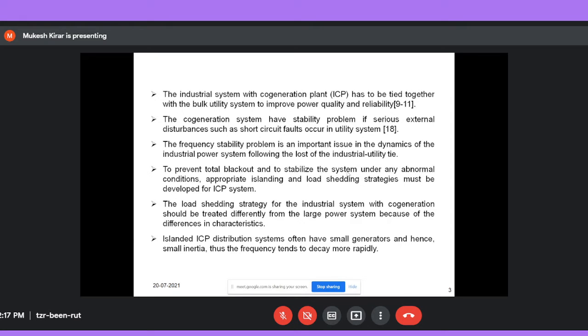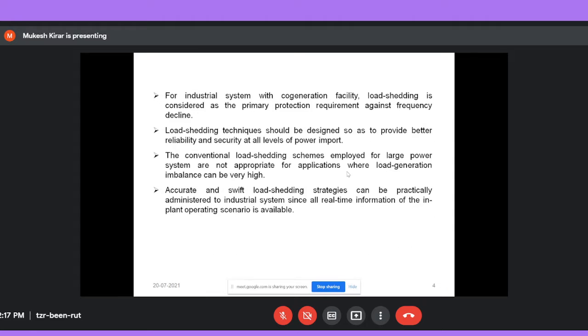At the same time, if there is an excess of generation and less load, then there will be a problem of over frequency. So in both cases, whether generation is less or more than the load, a frequency stability problem will occur in the industrial system. For that, in an industrial system with a cogeneration facility, load shedding is considered a primary protection requirement. Suppose there is less generation after islanding, so the in-plant generation is less than the connected load. What will happen? Frequency will decrease.